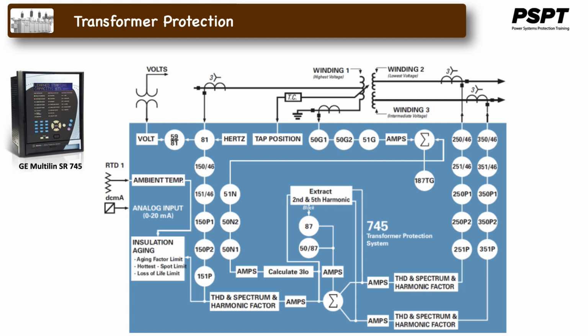This is the functional diagram for the relay. It may appear a little bit confusing because each one of the function numbers associated with one of the individual 3 windings of the power transformer are prefixed with a 1, 2, or a 3, depending on the winding that it's associated with. For example, winding 1, the prefix on the function numbers is 1. For winding 2, the prefix number is 2. And for winding 3, the prefix number is 3. So if you just remove those winding numbers, it becomes a little bit more obvious. The standard function numbers are as listed here on the diagram. As you can see, it pretty well covers the entire spectrum of protection that's required for the transformer and then some.